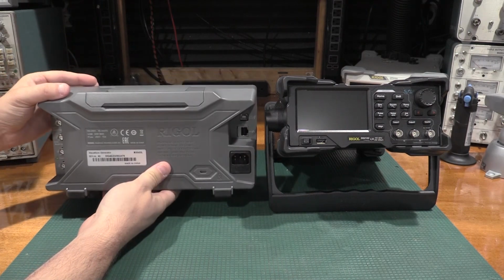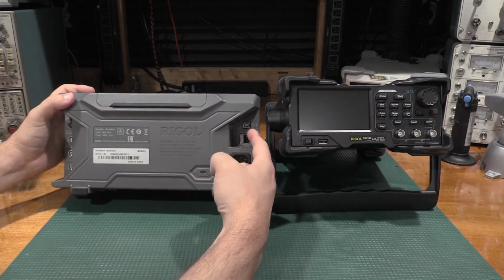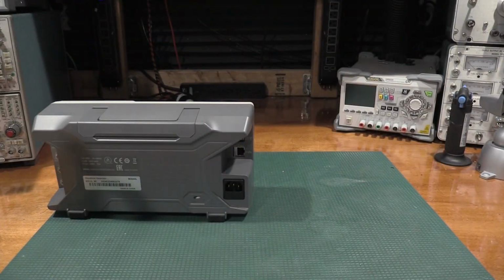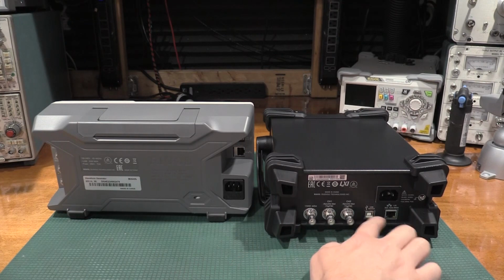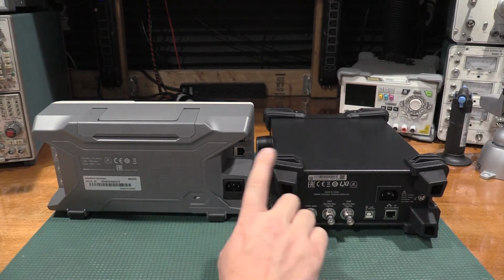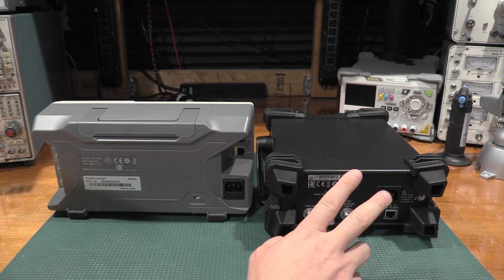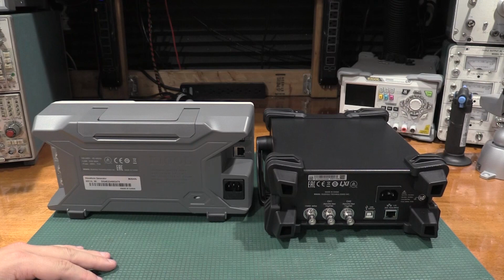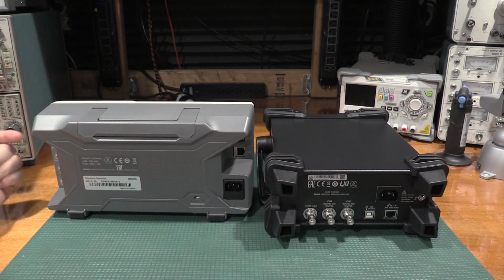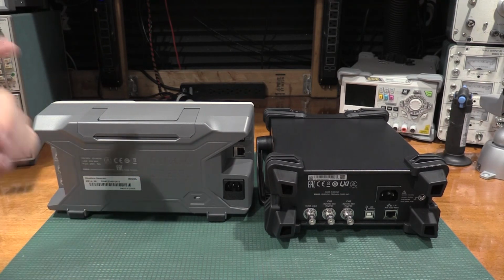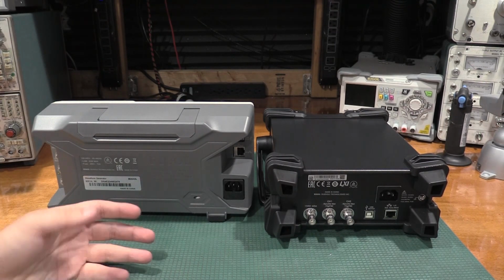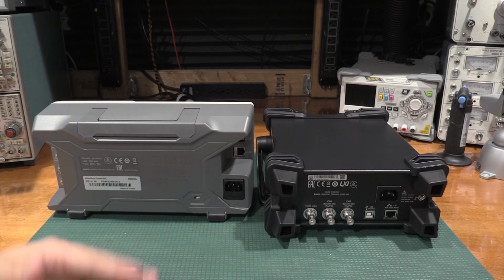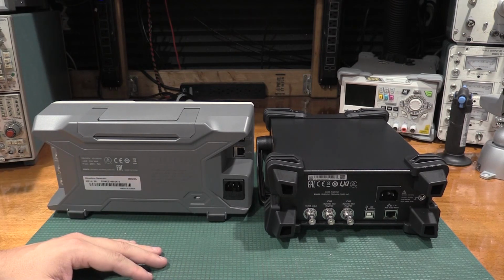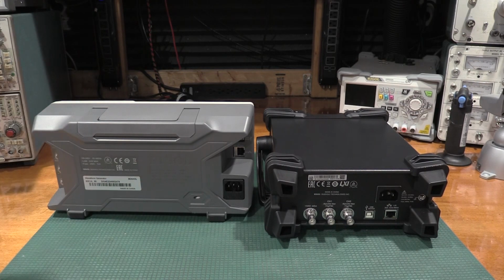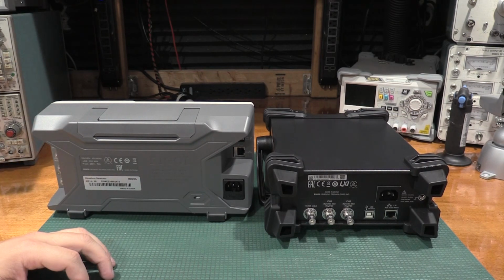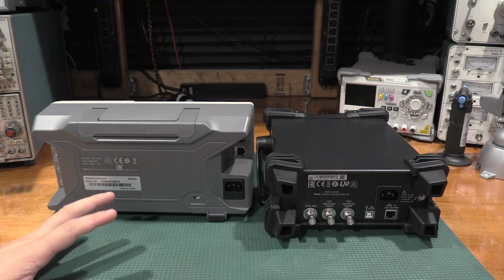So on the back of these units, we have the usual USB, LAN. And this is one of the important parts for the 2000 series that I wanted to grab, because I can use the rubidium, which I am planning on using for both of these units. I'm going to configure them for 10 megahertz in, and these are going to get two spots on the rubidium frequency standard. That's just going to stabilize the clocks and tighten up the frequencies. So when I ask for a frequency from one of these units, I should be very, very close. We'll test that actually when I get these fired up, as well as look at some of the critical scope calibration parameters a little bit later.